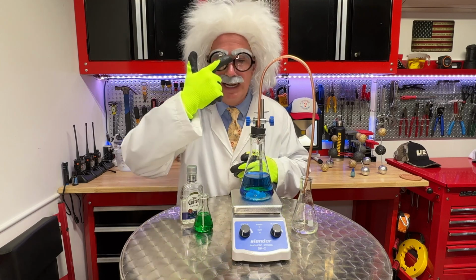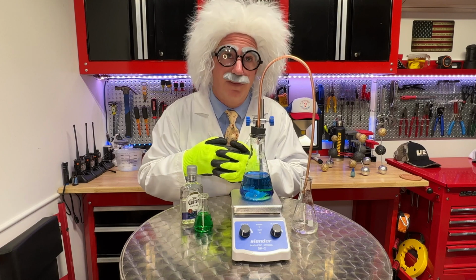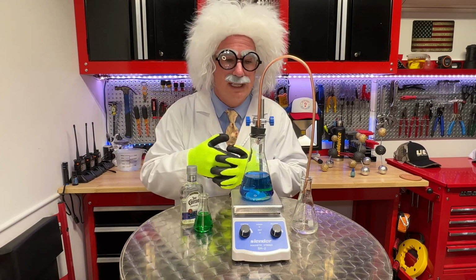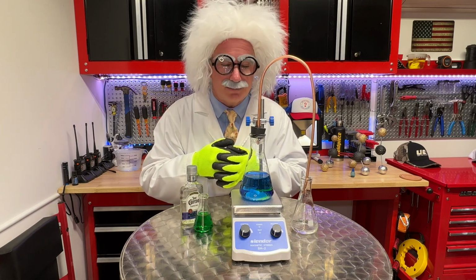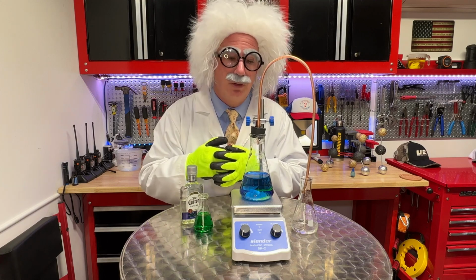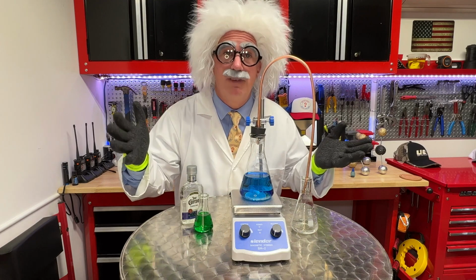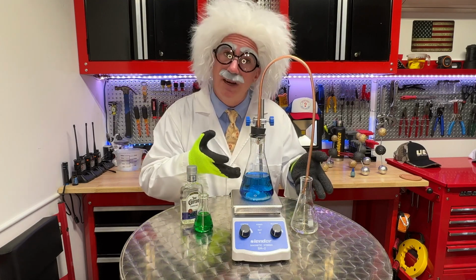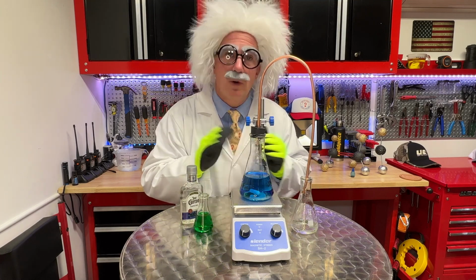not the other. Now, most of our manufacturers will tell us that even chemicals like R454B, which is going to be one of our new refrigerants in place of R410A on new equipment, it has a glide of a couple of degrees. And we're being told that it's not significant enough to need to replace all of the refrigerant unless it has been leaking for a very extended period of time. As you can see, even in this little experiment, it took a half an hour, 40 minutes just to be able to remove that small amount of ethanol. So we're not as concerned.